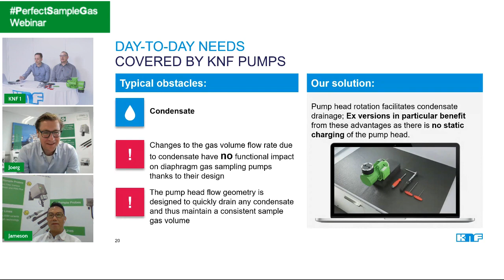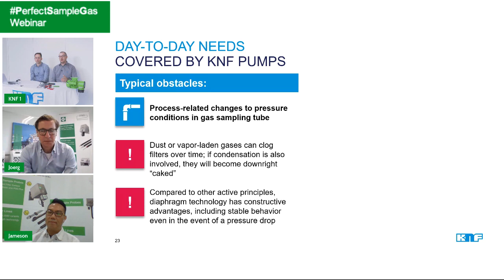Last but not least, and I think this is the most important topic that you want to see when we talk about the new pumps with brushless DC motor: what if the conditions in the measuring system change? What can we do? You of course need a reliable measurement. You want a constant flow, and we talk about process-related pressure drops. You mentioned one before. The most common thing, I guess, is a clogged filter. In the filter, we have dust, we have condensate, the filter becomes clogged, and therefore it has an impact on the flow rate of the pump and on the measuring.